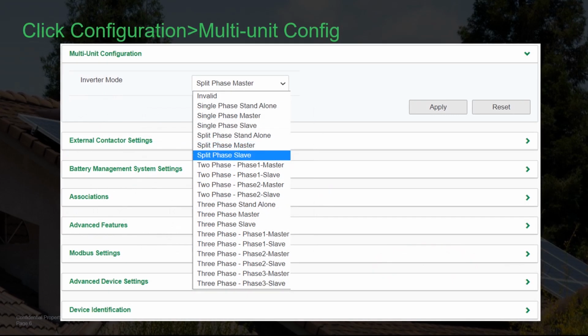For a multi-unit system, each XW Pro has a dedicated configuration menu. XW Pro defaults to split-phase master and is assigned device number 1 by default, so you really only need to program the slaves. Navigate to Configuration, Multi-Unit Config and select Split-Phase Slave from the drop-down menu. Click Apply. You can see there are many selections in the multi-unit config menu.